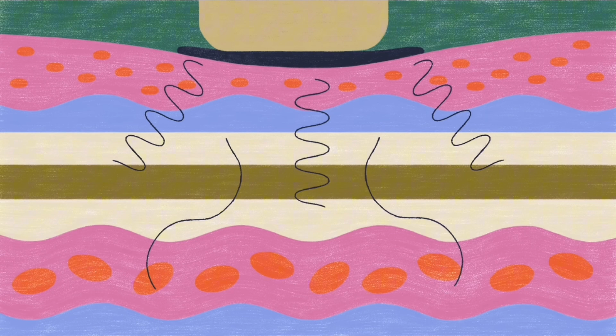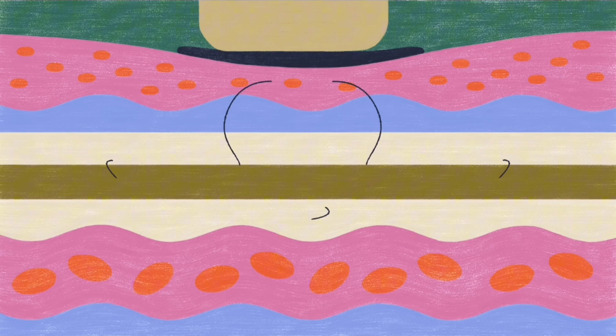To get a complete picture, waves need to reach different depths in the patient's body, bypassing some tissues while echoing off others. Since longer low-frequency waves penetrate deeper than short high-frequency ones, multiple frequencies are often used together and composited into a lifelike image. The operator can then zoom in and focus on different areas. And since ultrasound machines send and receive pulses of waves in real time, the machines can visualize movement.